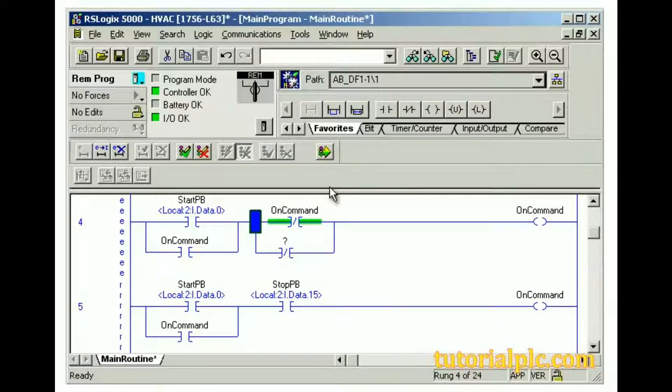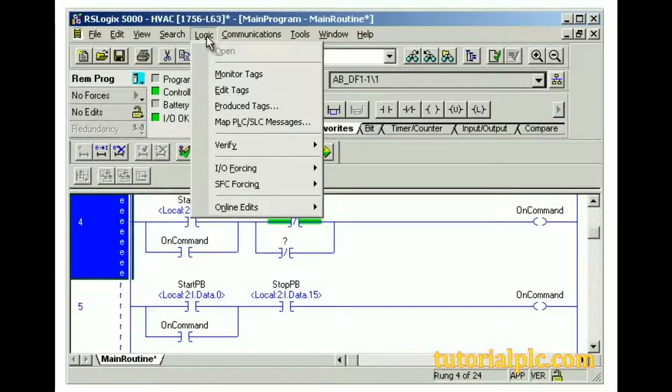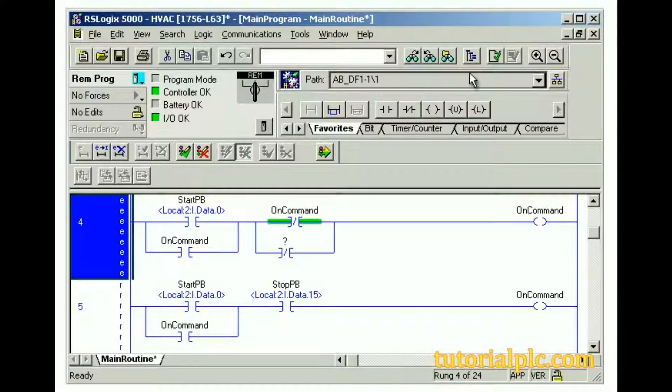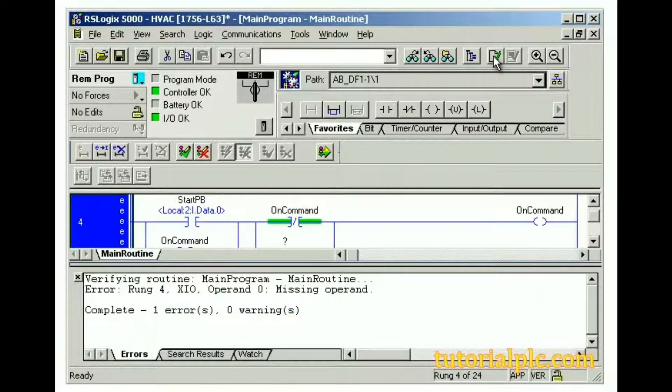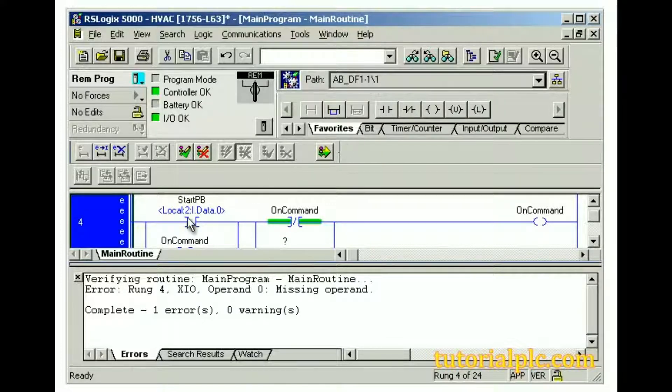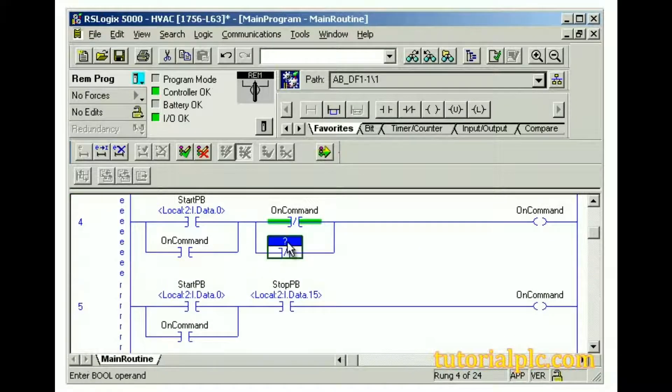Let's begin. To verify a rung, we can right-click the rung and select Verify Rung, or we can open the Logic menu and then select Verify Routine. Or to quickly access the Verify Routine option, we can use the Verify Routine button on the toolbar. Errors found in the verification process are displayed in the Errors tab of the output window. We must then correct any problems according to the errors and then verify the rung again.